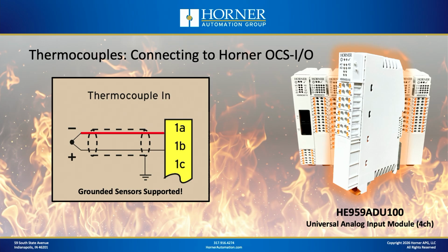One of the modules with OCS-I is the ADU100. That is a universal analog input module that can handle not only 16-bit 4 to 20 milliamp and 16-bit 0 to 10 volt, it also can handle direct conversion of thermocouple and RTD readings into the system. In the case of thermocouples, you can see there are 3 connection terminals for each channel. And in the case of thermocouples, the negative lead of the thermocouple is connected to the A input, and the positive lead is connected to the B input. It's also important to note that OCS-I does support grounded thermocouples.